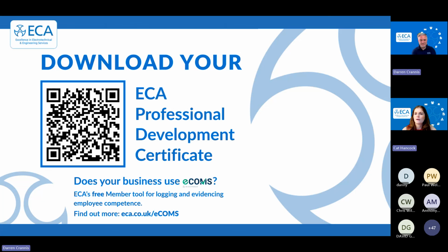And then just another quick one. Would an IT guy not be classed as an ordinary person? Typically in that case, and our risk assessor is really good at this, they'd be skilled in IT, but not necessarily skilled in electrical, but we've got to look at the risks there. So we're getting that circuit to that cabinet safely, using ADS for that circuit to that commando outlet. Typically, the electrician will be plugging in the PDU inside that cabinet, and the cabinet will all be bonded where it needs to be. Earthing's in place, ADS will happen.